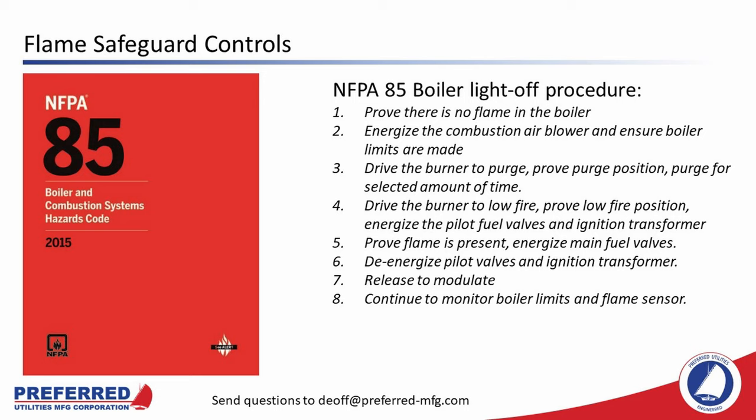Some modern flame safeguard controls include a function called early spark termination. The controller energizes the pilot valves and ignition transformer to light the pilot, then after five seconds de-energizes the ignition transformer and uses the flame scanner to ensure the flame is still lit without the ignition transformer. Ultraviolet scanners can sometimes see the igniter spark and not the pilot flame, which could cause the flame safeguard controller to open the main fuel valves without a pilot flame present — which could be dangerous. By terminating the spark early, the flame scanner can only be satisfied by a real pilot flame.